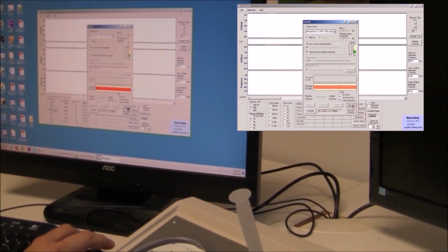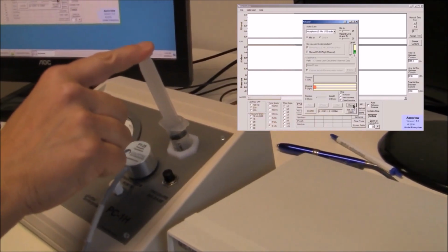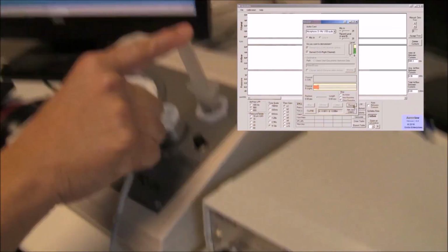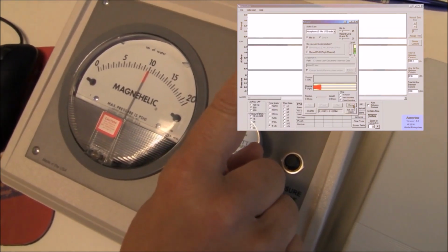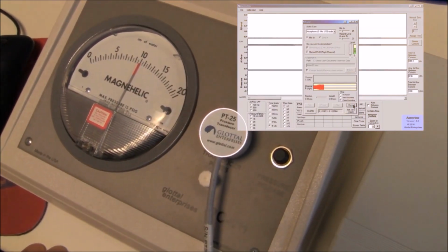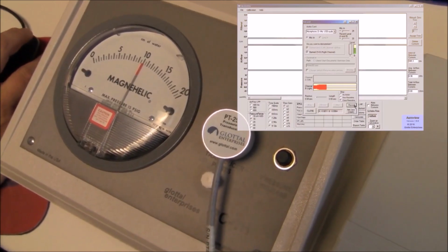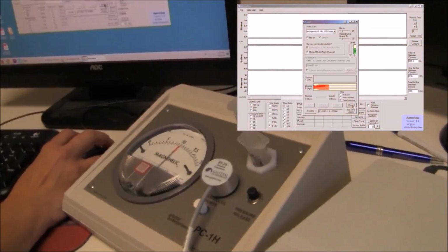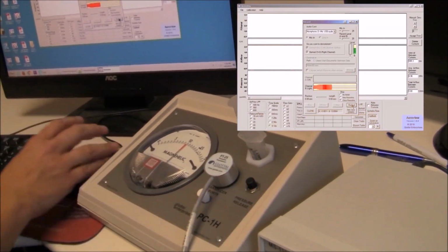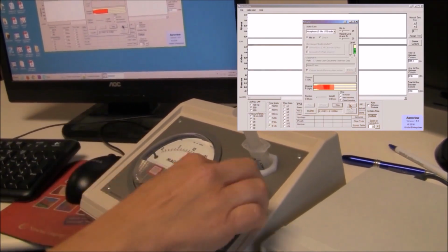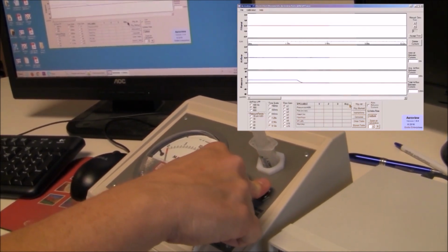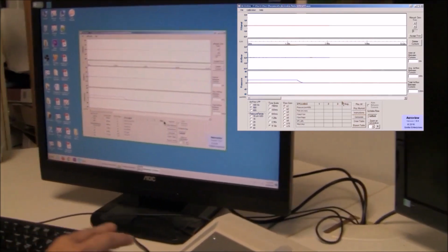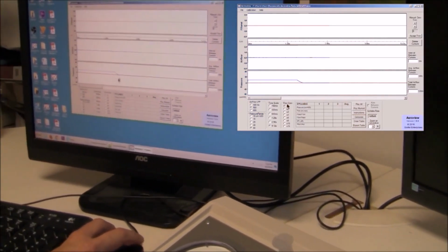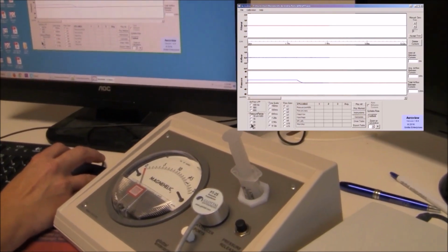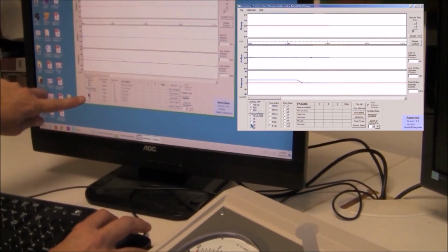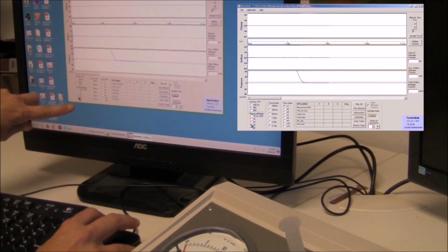And then after I click set 0, I'm going to put 10 centimeters of water, 10 centimeters of pressure onto the calibrator. Now I'm going to press record, and then I'm going to press the pressure relief switch and hold it, and you will get this waveform, which looks great. And then if you want to see it, you can change the pressure range here.